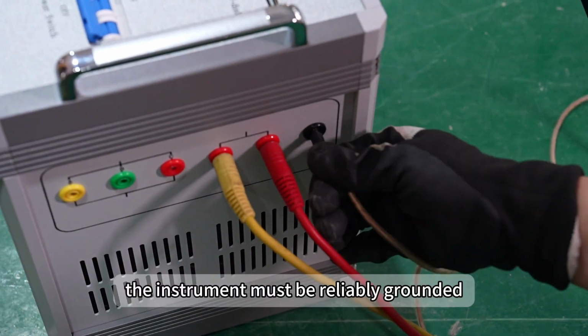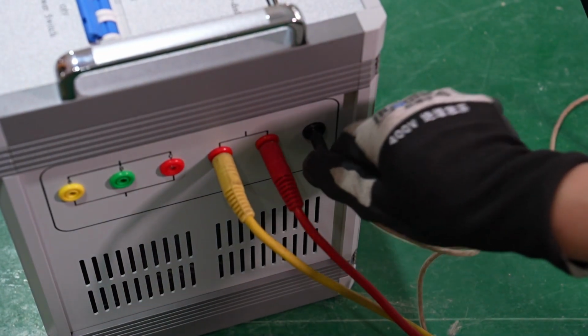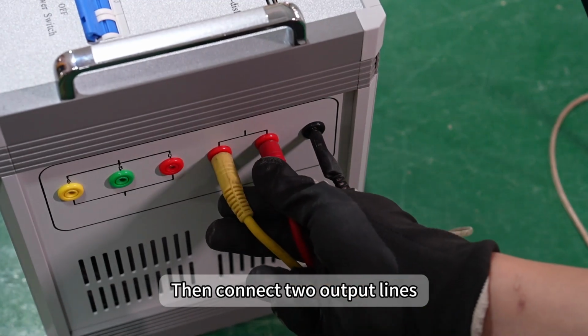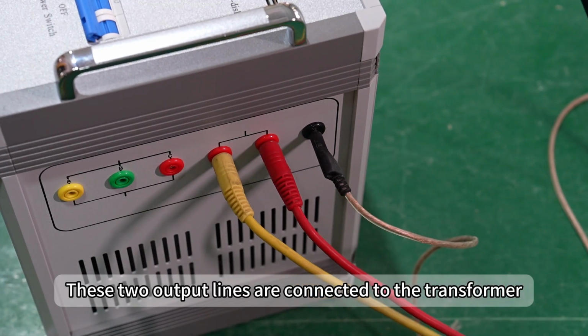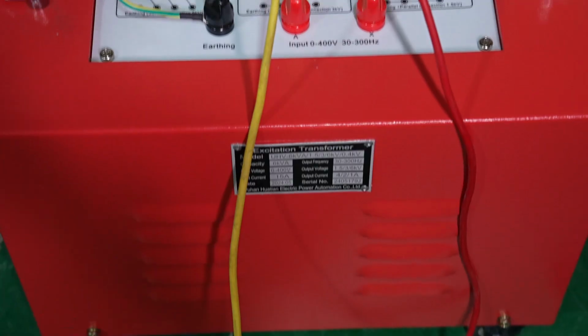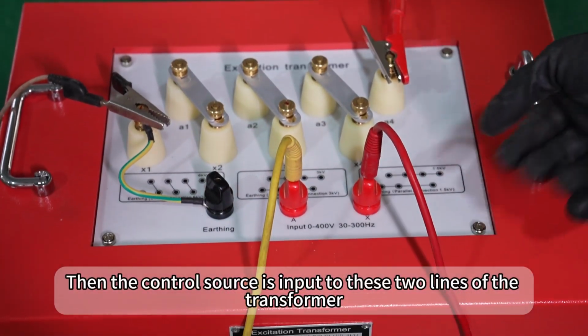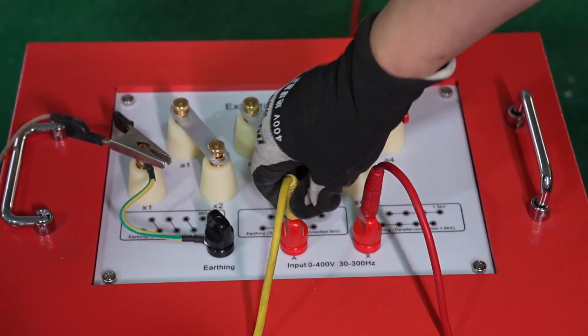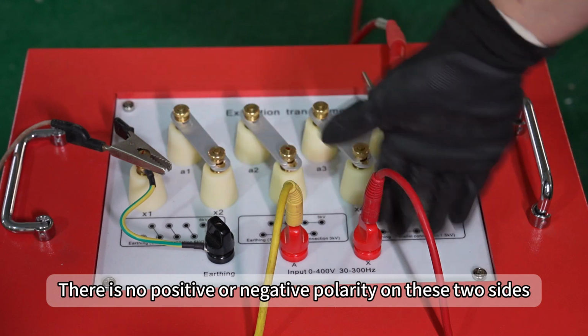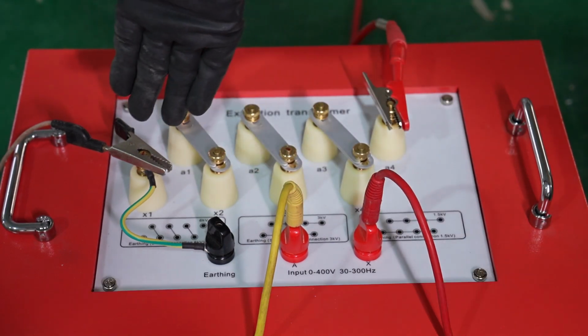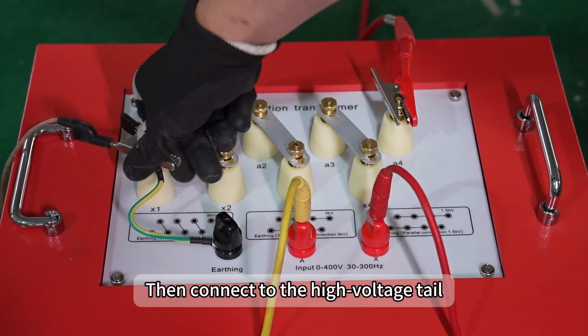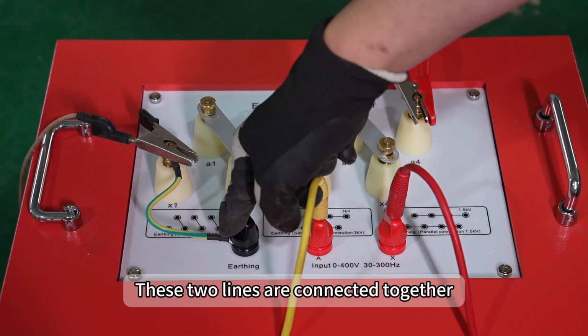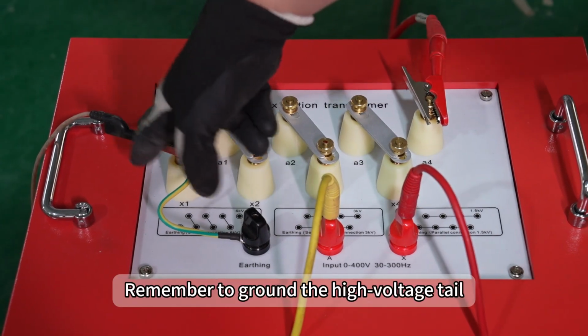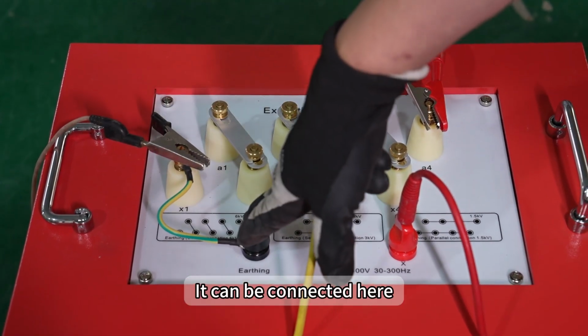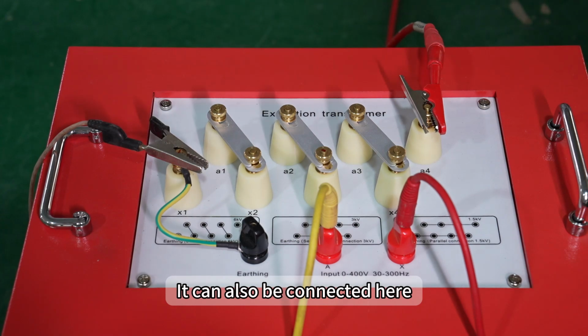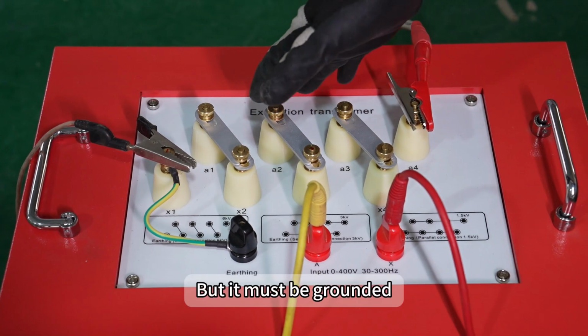First, the instrument must be reliably grounded. Then connect two output lines. These two output lines are connected to the transformer. Then the control source is input to these two lines of the transformer. There is no positive or negative polarity on these two sides. Then connect to the high voltage tail. These two lines are connected together. Remember to ground the high voltage tail. It can be connected here, it can also be connected here. But it must be grounded.